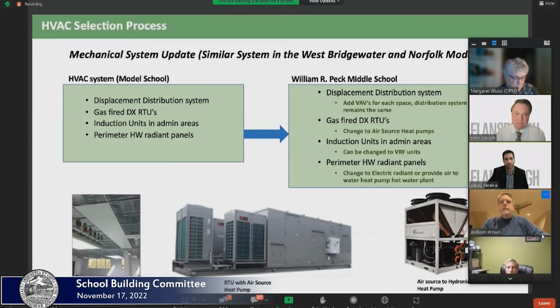Thanks, Ken. I wanted to discuss from an MEP standpoint what it would mean to take a 2014 vintage design and apply it to current projects that will be all-electric. This slide focuses on mechanical, but I'll briefly cover electrical design impacts. From an electrical standpoint, we'd expect the service size to increase about 20% compared to a building with gas, and the generator, if freeze protection is required, would roughly double in size. Lighting controls would need to meet the latest energy code requirements, meaning lower light power density, new vacancy sensing requirements, and switched receptacles in certain locations.